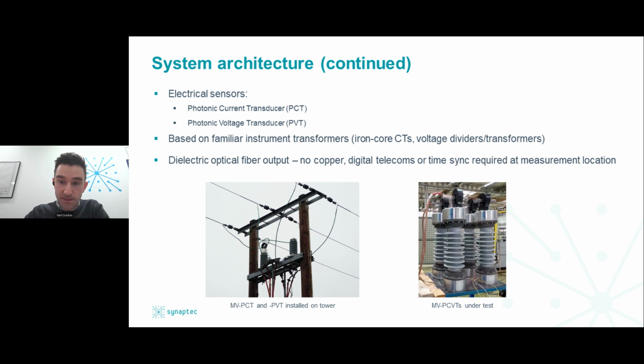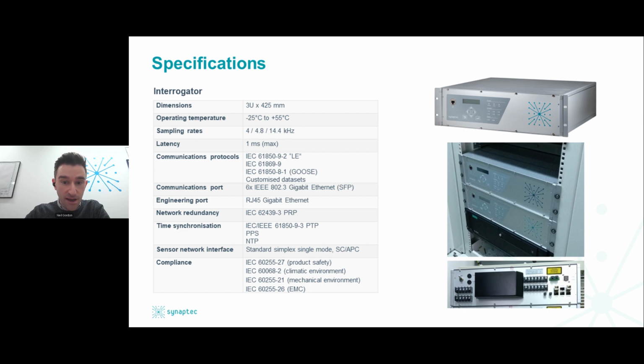And here you can see just a couple of images of the medium voltage electrical sensors. So you have the photonic current and the photonic voltage transducers. As you can see, these are a very familiar form factor to standard devices in the sector because they are simply optically instrumented standard CTs and VTs, and they maintain safe dielectric fiber optic output. Because these require no copper or digital telecoms or time sync at the measurement location, their footprint and installation times are kept very low, so there's minimum disruption from the installation. And on the next couple of slides, I'll just take you through some specifications for each of these devices.